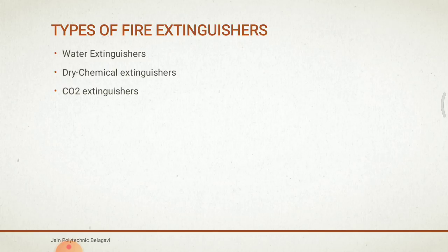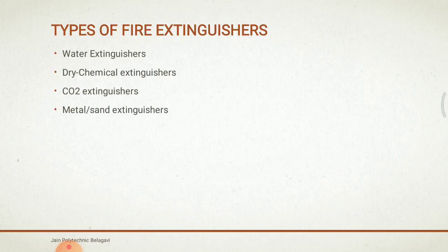There are two kinds of dry chemical extinguishers: Type BC and Type ABC. Type BC extinguishers contain sodium and potassium bicarbonate, while ABC extinguishers contain ammonium phosphate. Metal and sand extinguishers are used for flammable metals and work by simply smothering the fire. The most common extinguishing agent in this class is sodium chloride (NaCl). Powdered copper metal (Cu), graphite, and basalt powders are also designed for use on lithium fires.